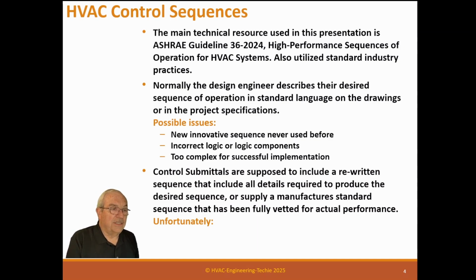Okay, so the way this is supposed to work is the engineer puts a sequence in English on the drawings or in the specification. The control contractor is supposed to take that sequence and rewrite it with the detail that he needs in it. Put all the timers in it, all the set points, all the entrance and exit points in that sequence, so it's what he's going to actually write. Now, we as a commissioner can look at that and say, okay, now we know what he's going to do. But that's not unfortunately what happens. What normally happens is the control contractor simply cuts and pastes the engineer's sequence on his submittal and says, that's what I'm going to do.